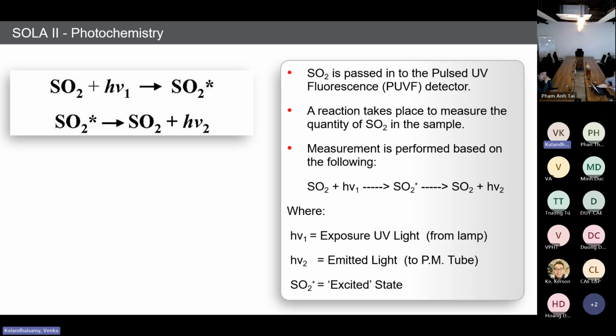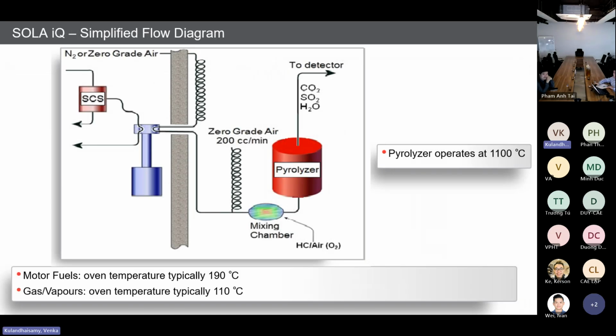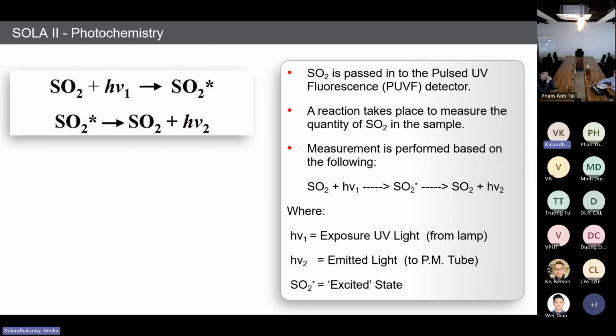Okay, so the hν2 energy is actually the emitted light. That emitted light is captured by the PMT tube, then the PMT tube converts the light energy to a current signal, which is equal to our ppm level. Is it clear? Yes. Okay. So this is the simple photochemistry happening on our PMT bench assembly. That means the PUV bench assembly.